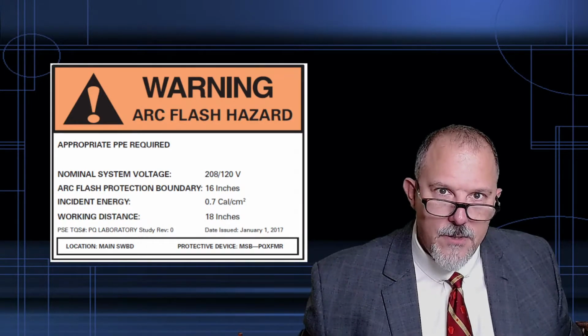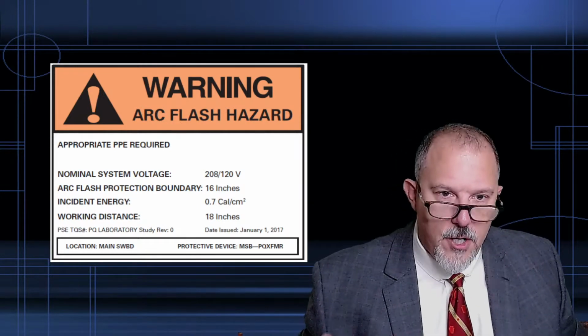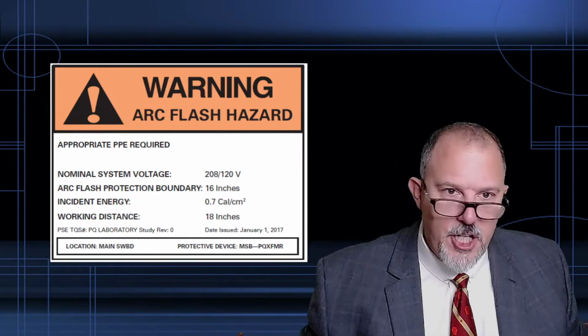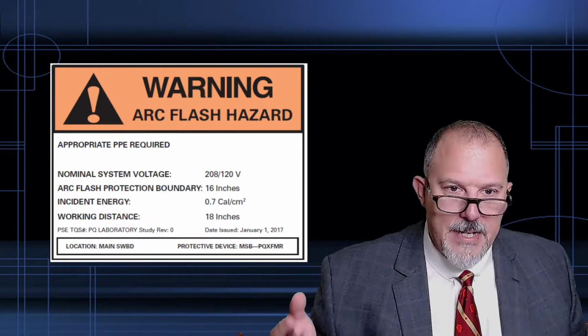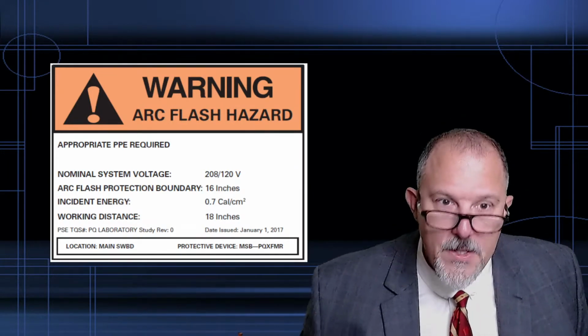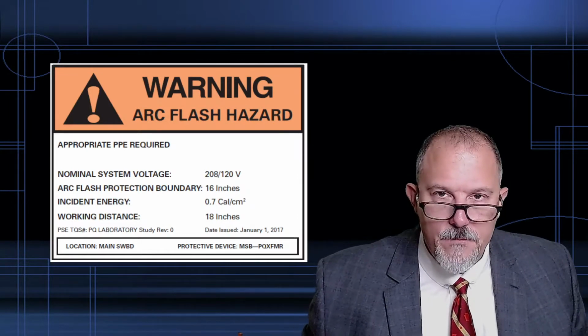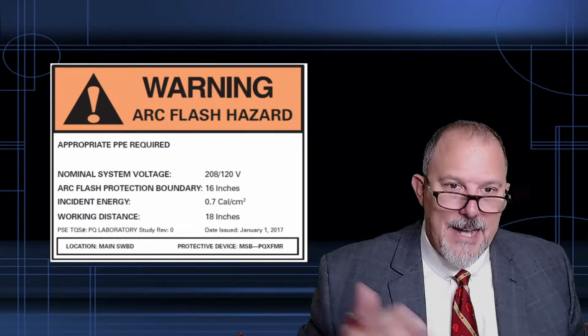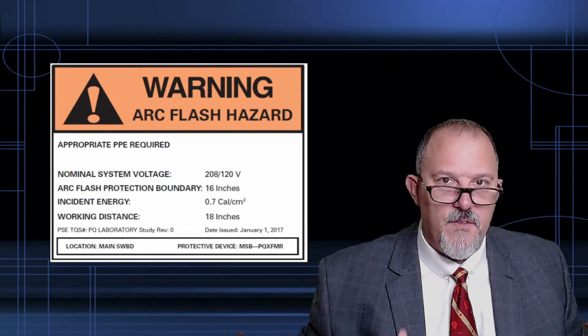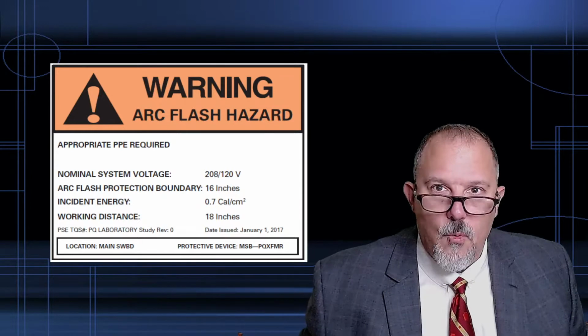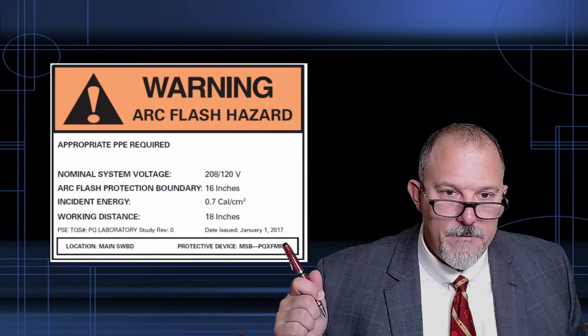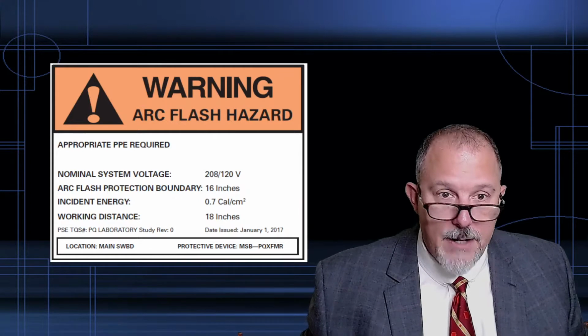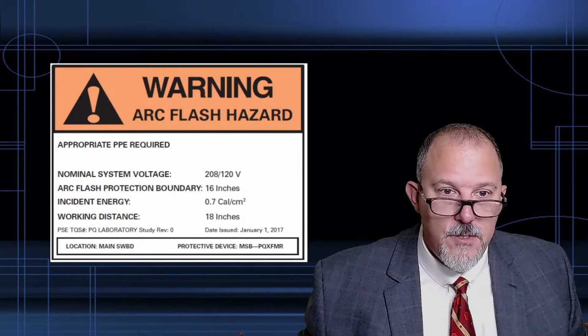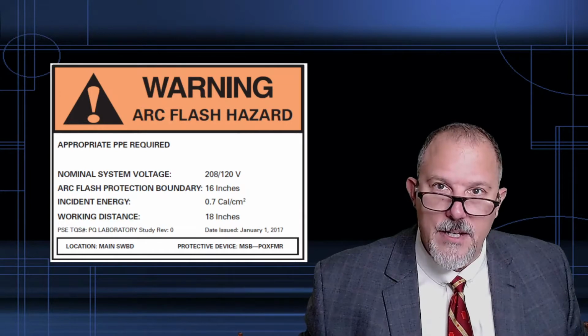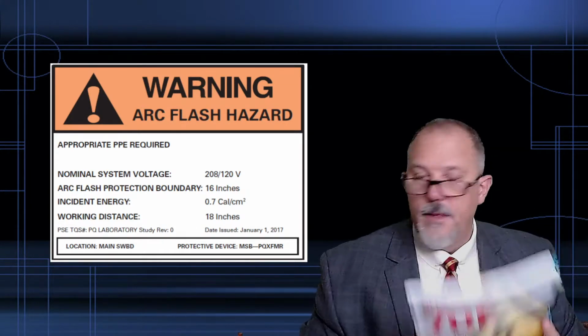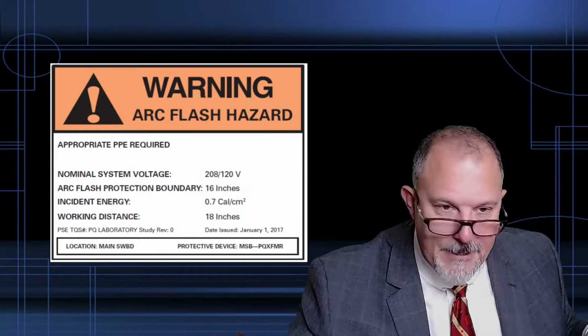That's a good question. The only argument I've heard on not putting the date is, what if nothing's changed in my facility and all of my tags are January 1st, 2017. Here I am 5 years later, and the incident energy is exactly the same. I have to go and scrape this off and put a new one on for what? Because of that date. And I would say just put a sticker over top of that has the new date. Anyway, there are ways around that, but it's not required in 70E.